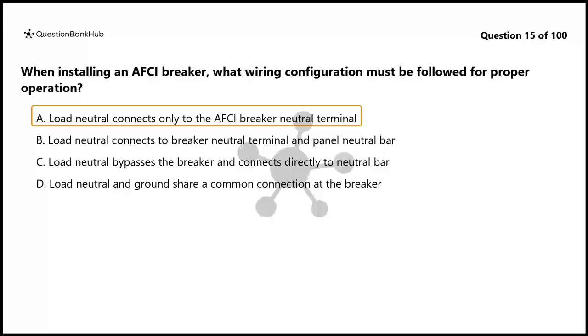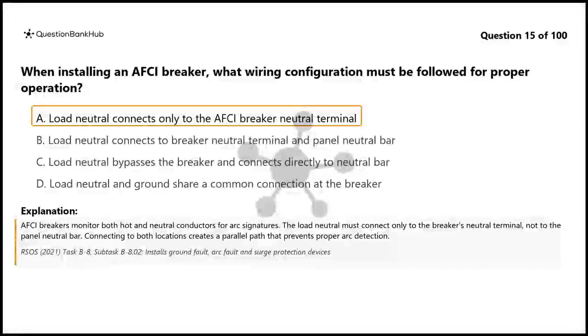The correct answer is A. Load neutral connects only to the AFCI breaker neutral terminal. AFCI breakers monitor both hot and neutral conductors for arc signatures. The load neutral must connect only to the breaker's neutral terminal, not to the panel neutral bar. Connecting to both locations creates a parallel path that prevents proper arc detection.